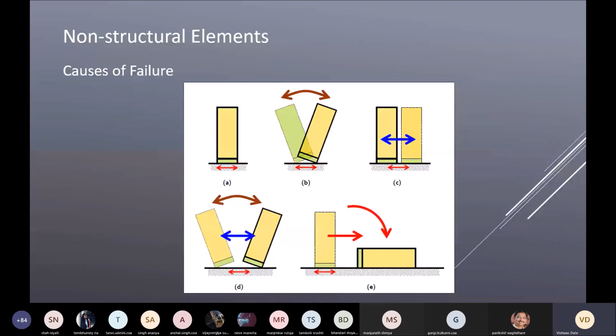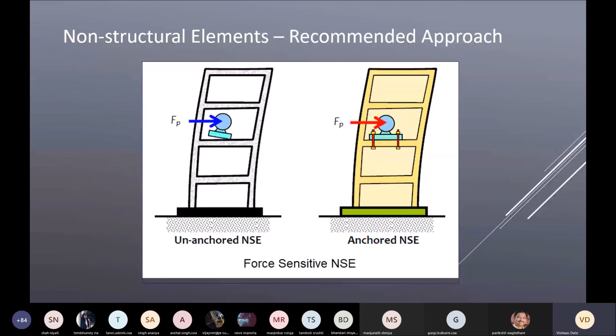So what is the recommended approach? If you have a pump, for example, technically speaking, by its own weight it can be easily supported because it will compress, it will push things down. But in case of an earthquake, there is a possibility of toppling action. So you need to have anchors on both sides of the equipment, or in short, 4 minimum anchors, so all 4 directions are secured from toppling.